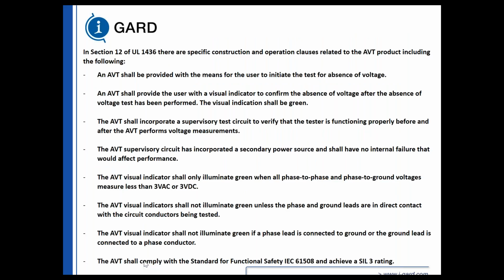So section 12 of UL 1436, there are specific construction and operation clauses that relate solely to the absence of voltage tester. An absence of voltage tester shall be provided with the means for the user to initiate the test. We have a test button there. It shall provide the user with the visual indication to confirm the absence of voltage after the test has been performed. So we have the 3 green blinking lights, and after the test is performed successfully, you have 3 green LED lights.